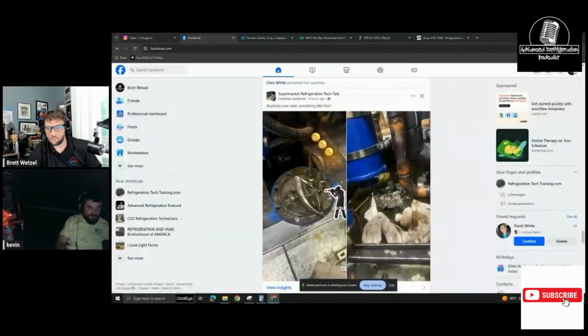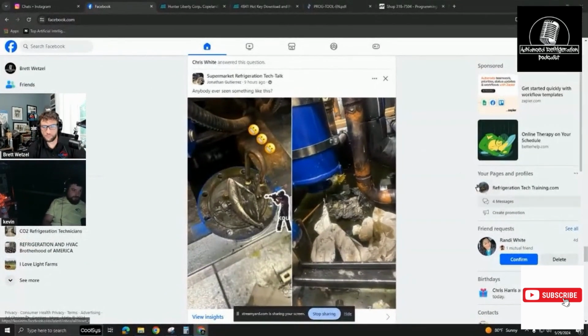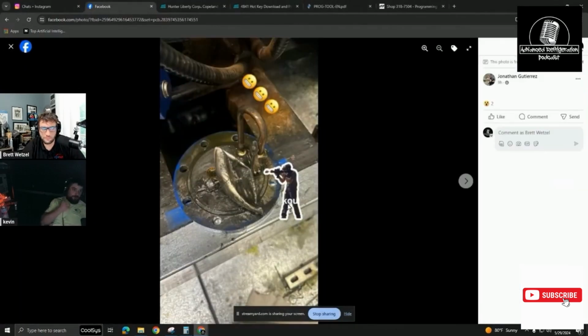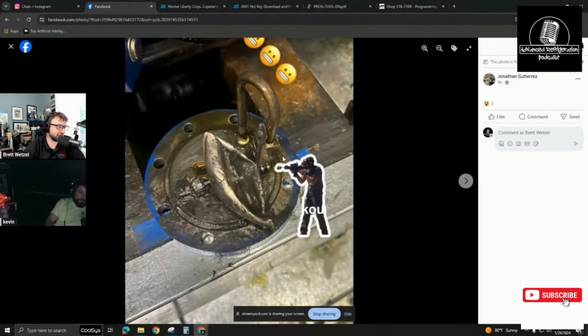I show up, one of them's got a blown valve plate, shut it off, and then I'm looking, and none of the oil's leaving the separator. Like, what the hell? Nothing in the sight glass, anything. So I'm looking around, like, what is that black piece in there? It's a chunk of material in there. It's just packed solid valve plate to the point where I'm fishing it out with a braze rod. Look at that thing. Oh, that thing is crushed. That's what I'm saying, dude.